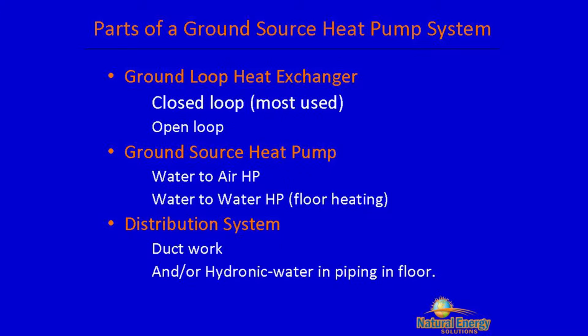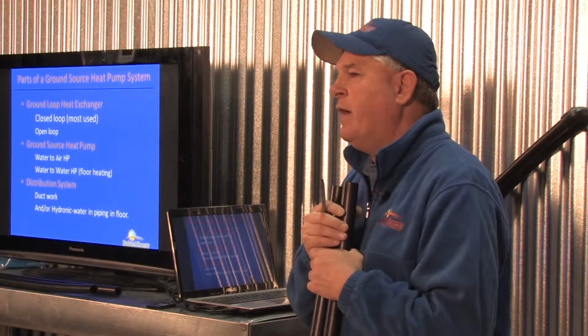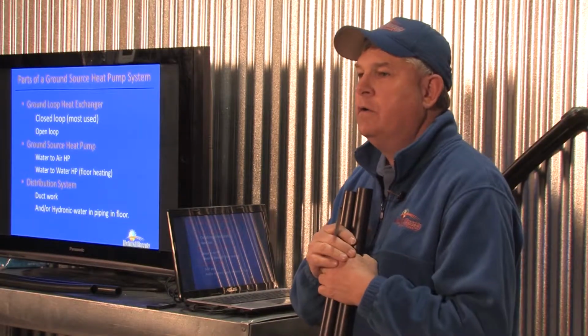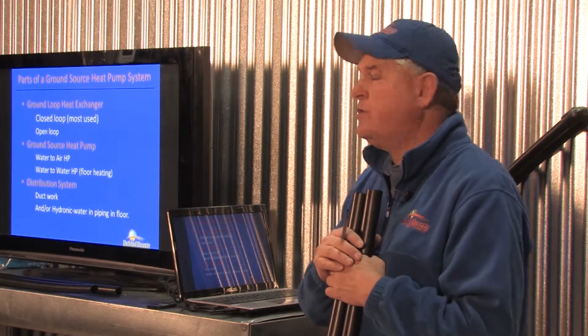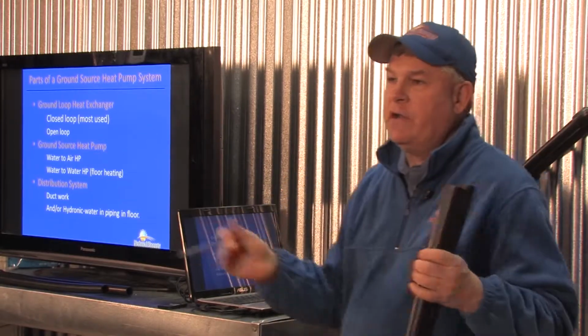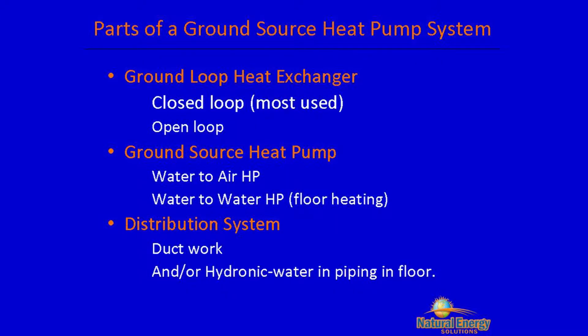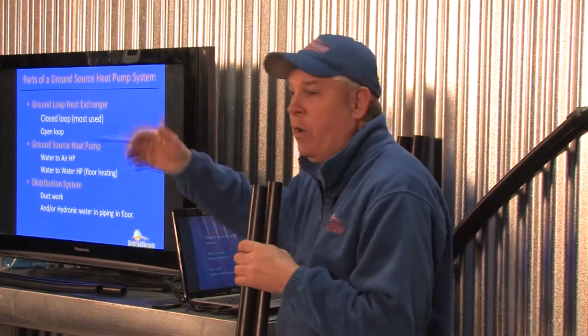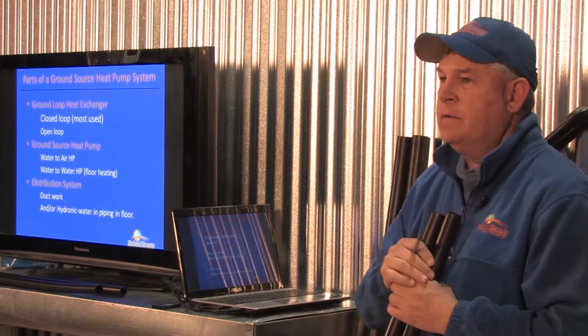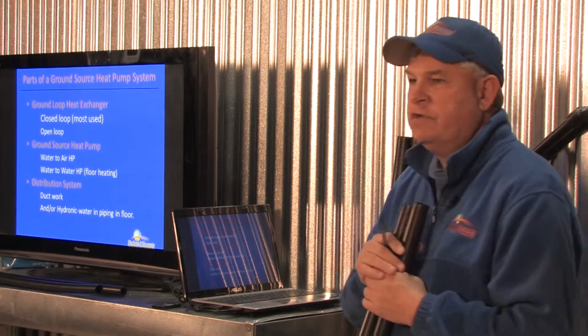Real quick review. 3 parts of a system. Ground loop heat exchanger. Well, when we have an open system, we don't have a heat exchanger, we just have a source of water. But we have a source of water coming in to get our energy from. The second part of the system is a ground source heat pump. They will all start with water, so they will either be water to water or they'll be water to air. Obviously, we're taking the energy from the water and transferring it either into a forced air or we're transferring it into another water, which we then distribute to the house. The third part is that distribution system. Radiant, hydronic, or some type of forced air system.